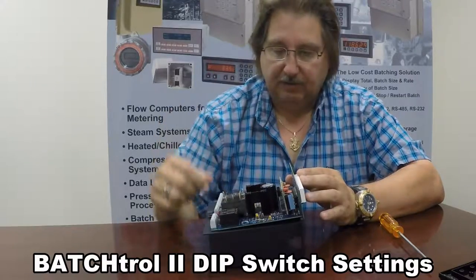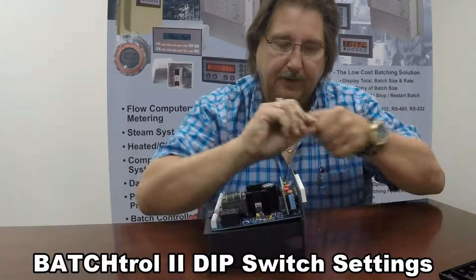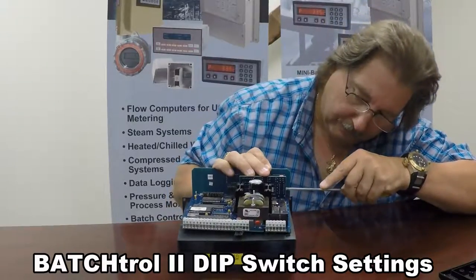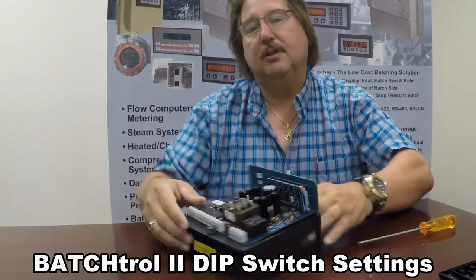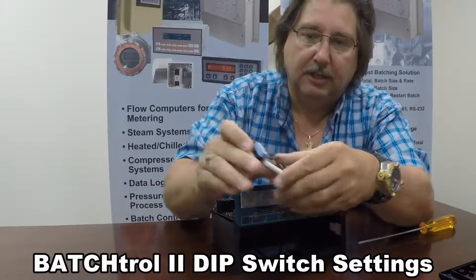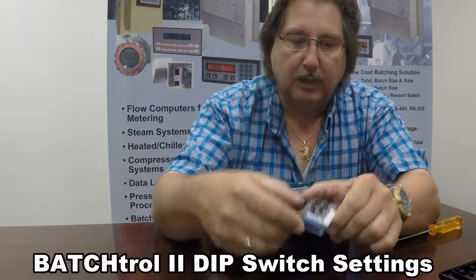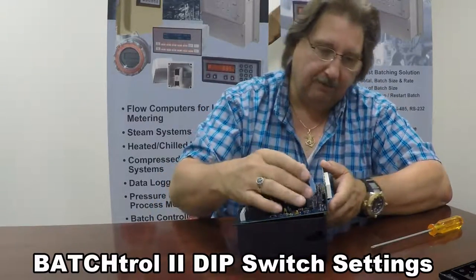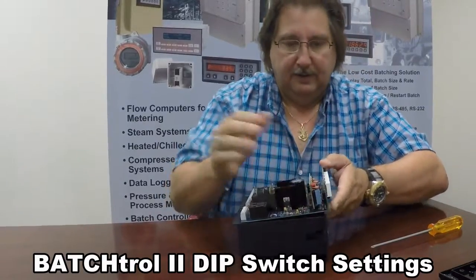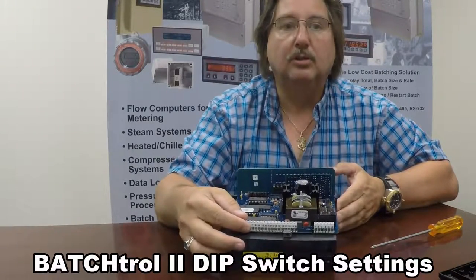If you have your Hall Effect sensor connected to the BATCHtrol, what you're going to need to do is go to switch four, which is this bottom switch right here. Simply take a screwdriver and turn the switch to the on position. You will see there's a little arrow pointing up, and switch four will now be up. What that does is it puts a 4.7K ohm quarter watt 5% resistor pulled up to VCC, so that your input is pulled up and your open collector or Hall Effect transistor will be able to drive the pulse to ground.